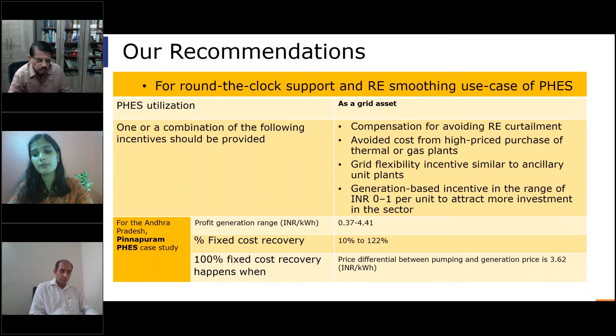Specifically for the case study, we saw the profit generating ranges from 0.37 to 4.41, which could be used for fixed cost recovery, ranging from 10% to 122%. If I have to do 100% recovery from this profit, then the price differential between pumping and generation should be around 3.62 rupees per unit.